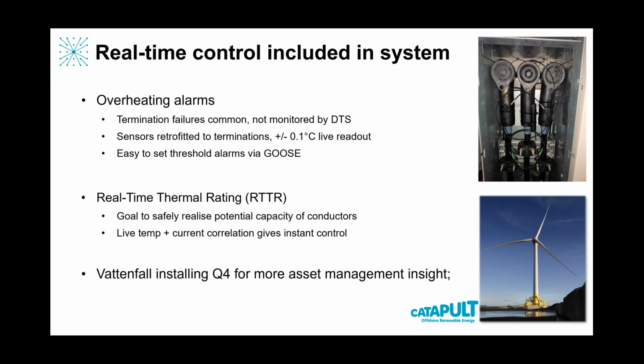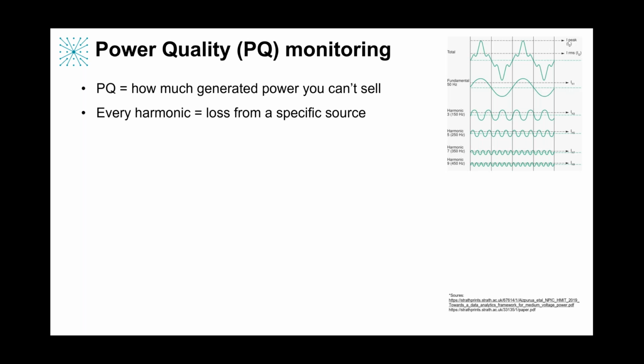And now, for these reasons, Vattenfall have also seen what we did at Leavenworth and asked us to install our first system at scale on one of their live wind farms, looking at instrumenting export cables. That's happening this quarter, and they're interested in something else which goes towards asset management and improved scheduled maintenance. That's monitoring power quality. If you don't know what power quality is, it's simply an electrical signal or power that you've generated but you can't sell because there's some kind of a loss. And every harmonic around the fundamental 50 Hertz signal, could be at 150 Hertz, which is the third harmonic, or up and up and up from that, is a particular loss from a specific source. If you can measure it, you can do something about it.